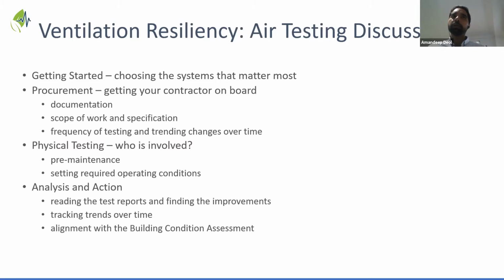it's sort of given. The two things that I see as the most important with a hospital: one is the IPAC needs. The second is making sure the pressurization, which is part of the IPAC, within the department or overall building is maintained. So if you haven't done the testing for a lot of these systems, my recommendation would be to start working with the critical systems around, for example, operating rooms. If you haven't tested those for air change rates in a while, that's probably the starting point.